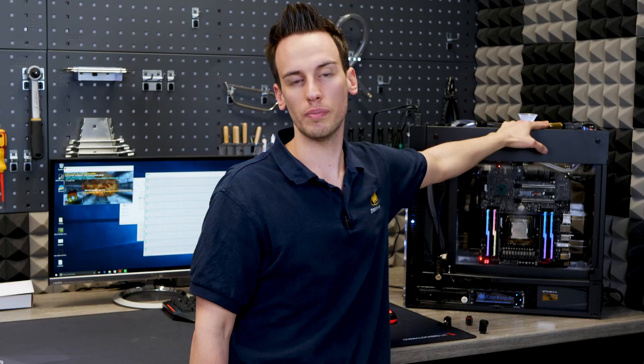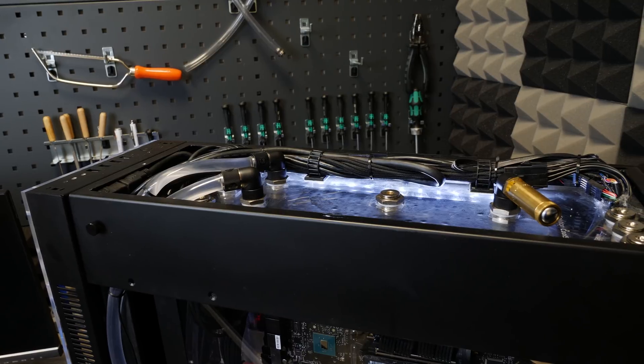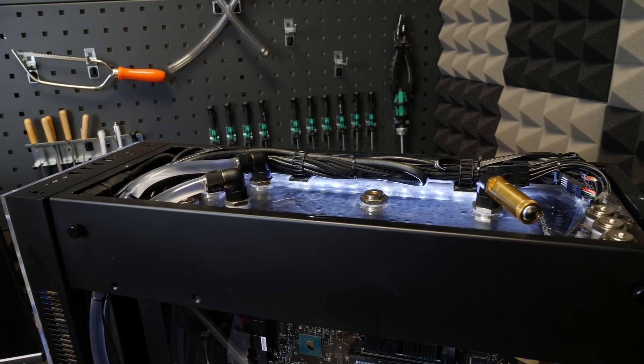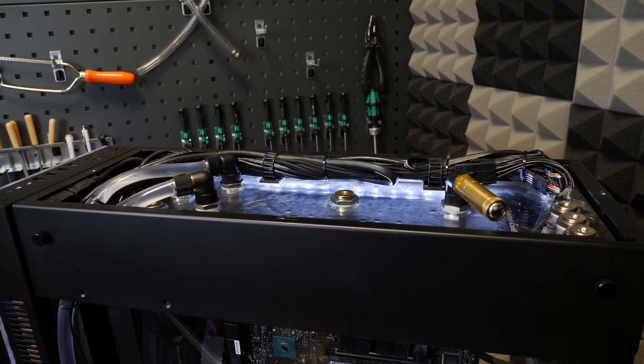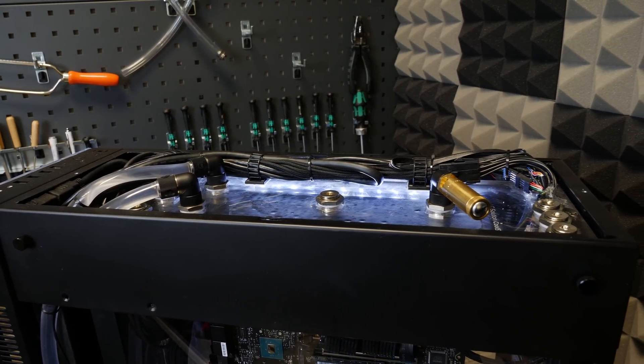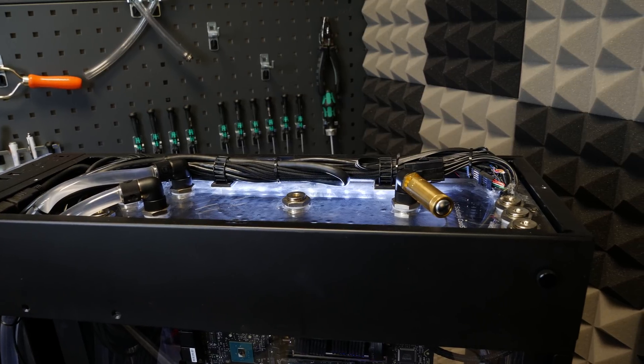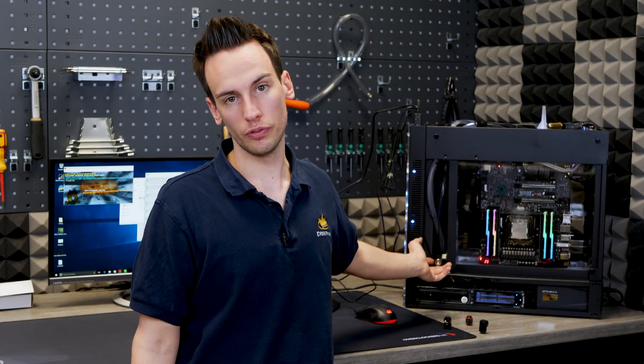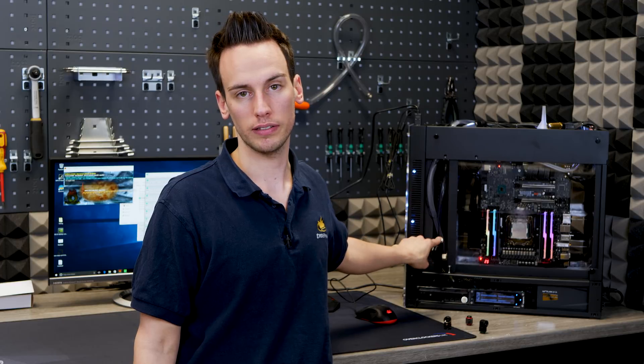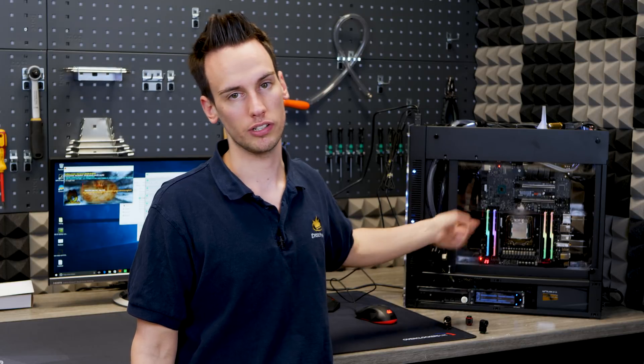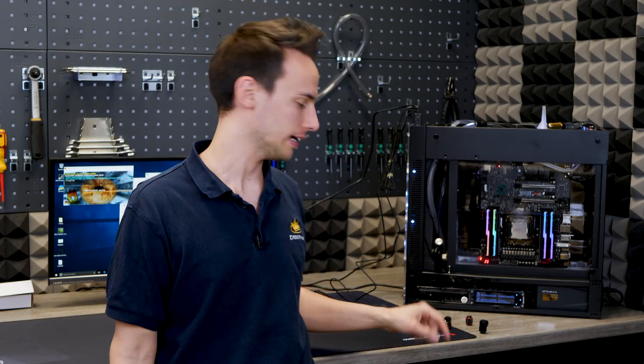On top here, you can see an emergency overpressure valve, which is set to one bar. It's mainly just to protect the tank. Usually you would not have a pressure inside there which is that high, because if the pressure is building up, then the condensation is also increasing. And then you don't have those issues. If you would want to remove the fluid, it's possible just by connecting a tube here and then just filling it back into the tank.